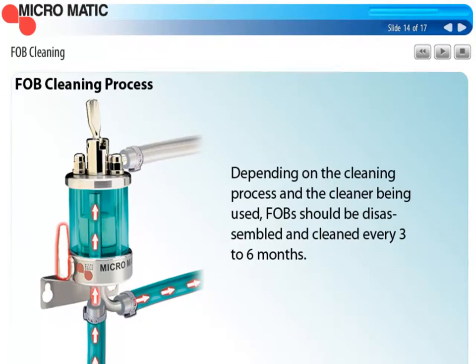Now here's a word of caution about disassembling and cleaning. The inside of the FOB must be cleaned with a rag. Do not use a brush on it. A brush will rough up the surface of the glass, and that can create a place for bacteria to grow. Use the caustic soda solution on a rag and just wipe clean the inside of the FOB. This should be done every 3 months for plastic FOBs and every 6 months for stainless steel FOBs.